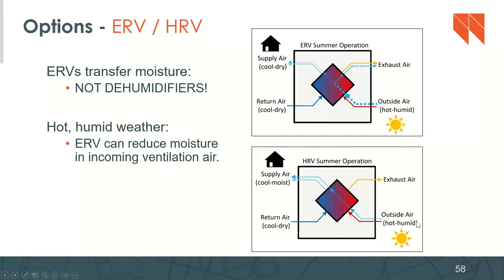And so as that hot outside air is being brought across the core, it may transfer moisture to the return air that is cool and dry, because your return air from the space, from your apartment, from your house, has been conditioned by your air conditioner. And then it's going to transfer some of that humidity from the outside air, and it's going to transfer it outside. Sorry, that was the bottom here is the HRV summer operation. The ERV summer operation is the same, i.e. there can be transfer. Sorry, I messed that up. This bottom part is the HRV summer operation. You can see the hot, humid air is just coming right along for the ride, right on inside.